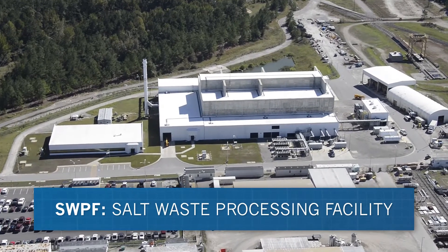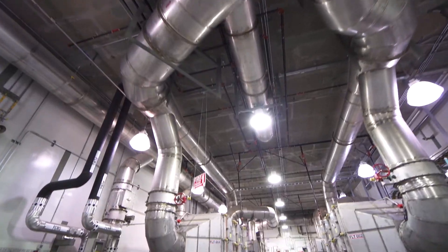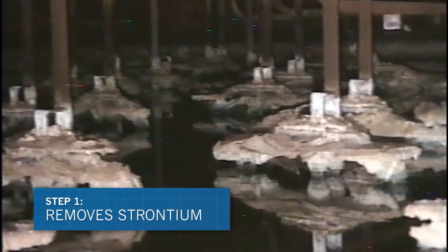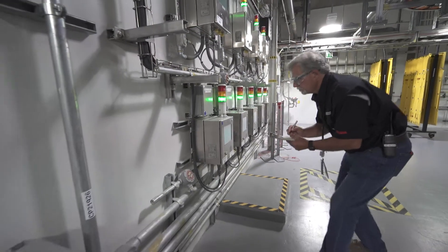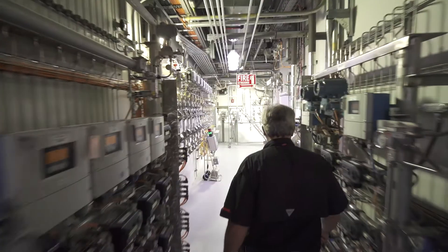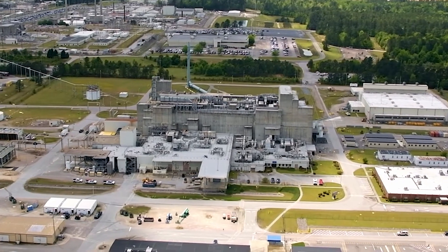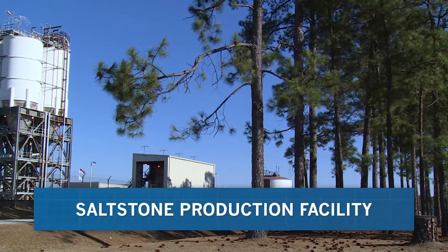The Salt Waste Processing Facility, or SWPF, began operating in 2021 and treats the salt portion of the waste through a two-step decontamination process. The first step removes strontium and long-lived actinides from the salt waste through adsorption. The second step removes radioactive cesium by extraction, using a special solvent and over 30 centrifugal contactors to mix and separate the solutions. Both the adsorbed waste and the extracted cesium solution are then transferred to the Defense Waste Processing Facility, or DWPF, and combined with the sludge waste for vitrification.